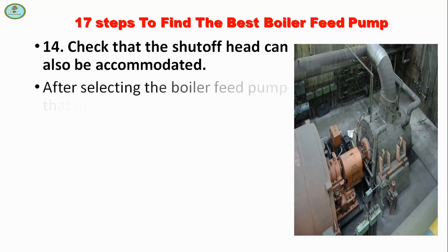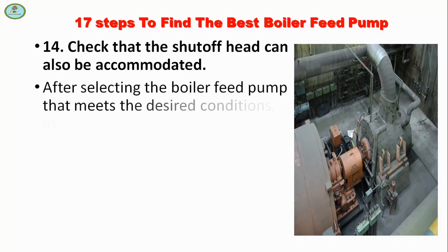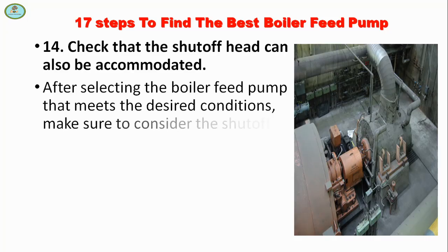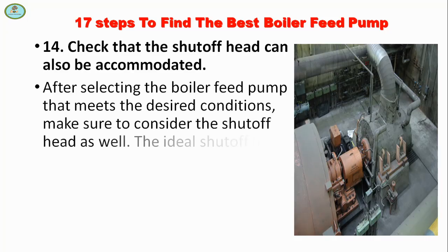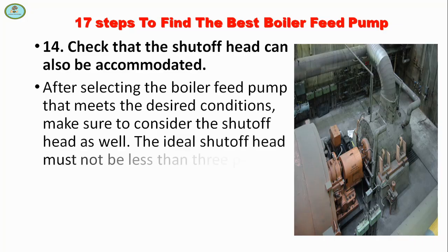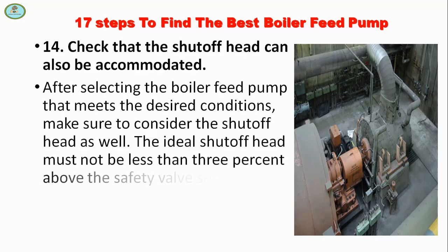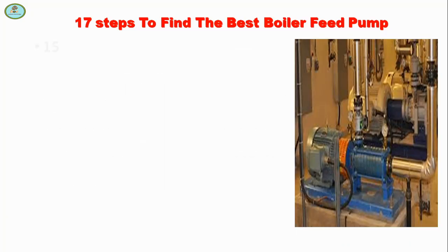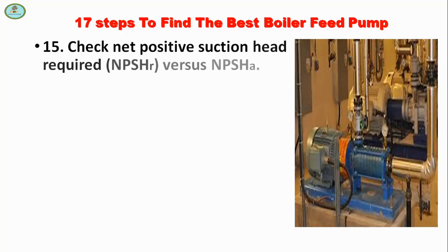After selecting the boiler feed water pump that meets the desired conditions, make sure to consider the shutoff head as well. The ideal shutoff head must not be less than 3% above the safety valve setting. Next is to check net positive suction head required versus NPSHA.